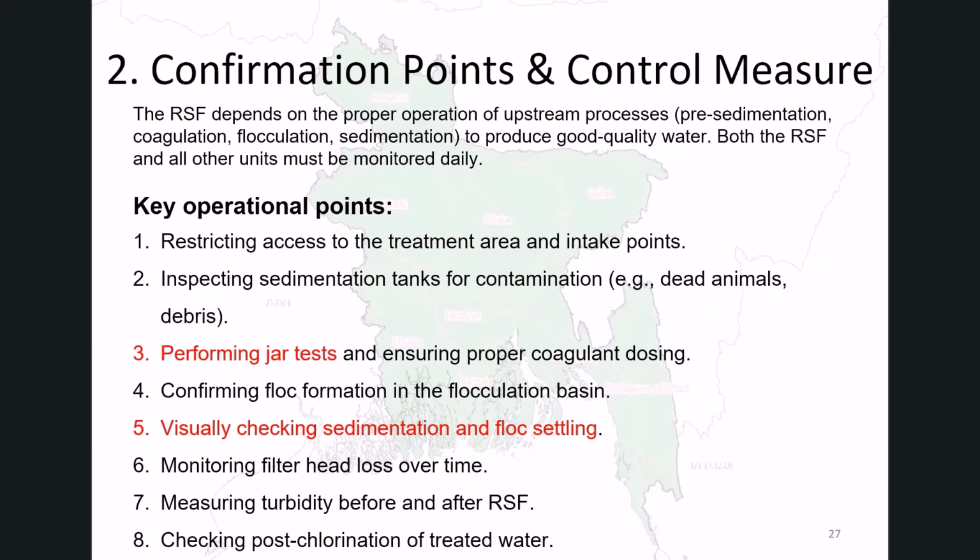Eighth, checking post-chlorination of treated water. This is very important to secure the water quality. Though the details will be explained in another session, the point is that the residual chlorine has to be measured at the water users' taps.